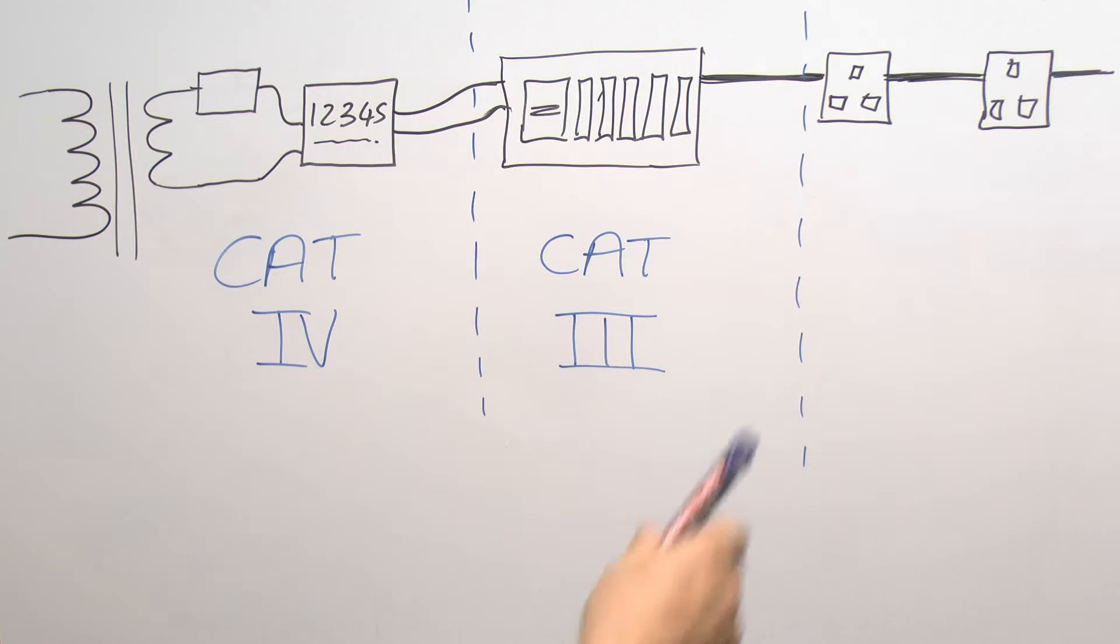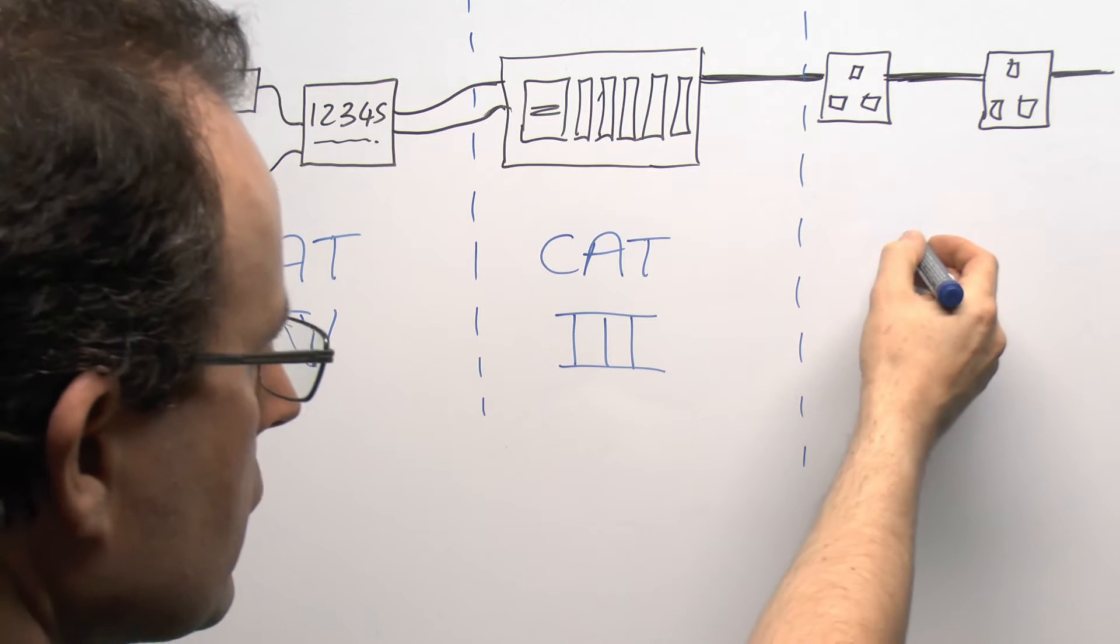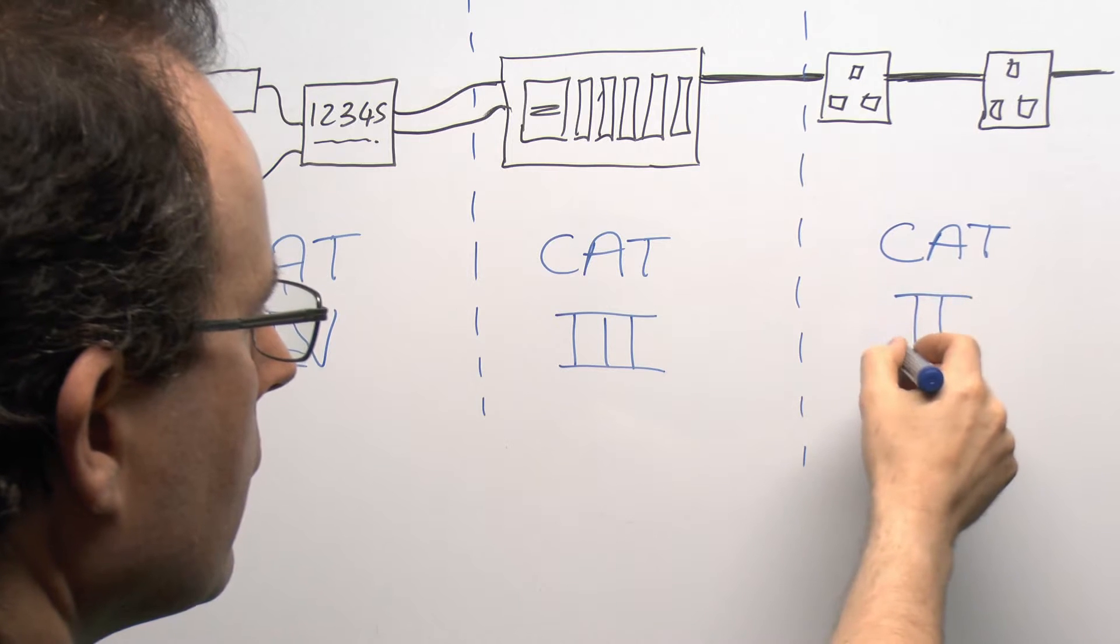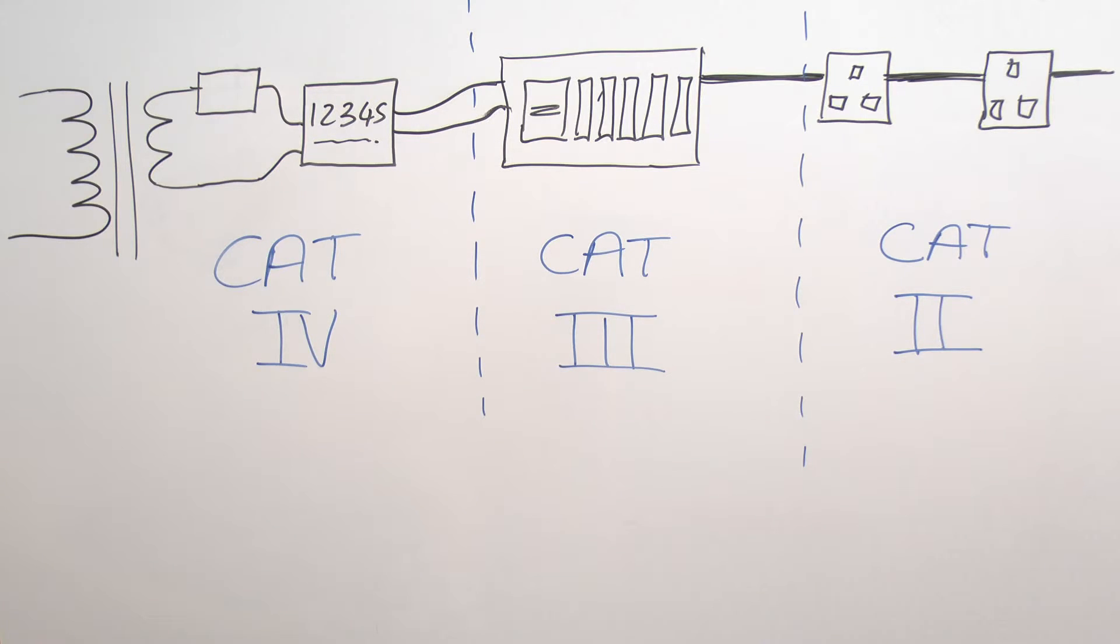And then of course further down the line you're going to have your individual circuits. So you may have socket outlets or lighting circuits or whatever else. And in those situations that's going to be a category 2. And again as with the others you're now much further away from the source of the energy here. So again the impedance is going to be considerably greater. And again the fault current there will be less than here and of course less than here. So as you're moving away from the source of the supply the impedance increases and the fault current of course will decrease. And of course then correspondingly the risk to actually anyone testing things there is reduced as well.